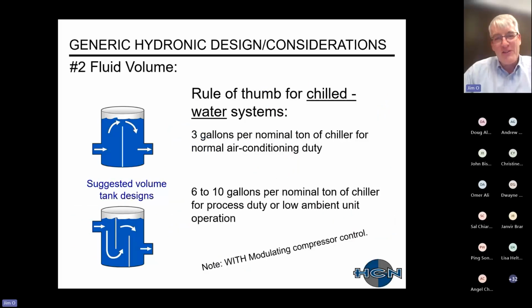All right. So next thing, number 2 out of 3 that I found out over the years, is for chilled water systems, you always have to consider the amount of fluid that's in your system. What will happen is that if you don't have enough fluid volume in your system, your chiller will basically end up cooling the chilled water too quickly before it can get to your load, and then your chiller will end up short cycling. So this is a chart from years and years ago that I recently looked up again, and it's still pretty relevant.